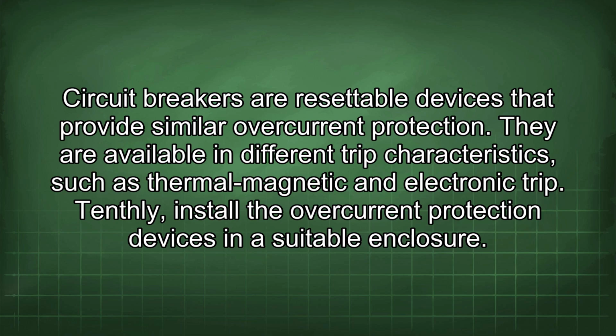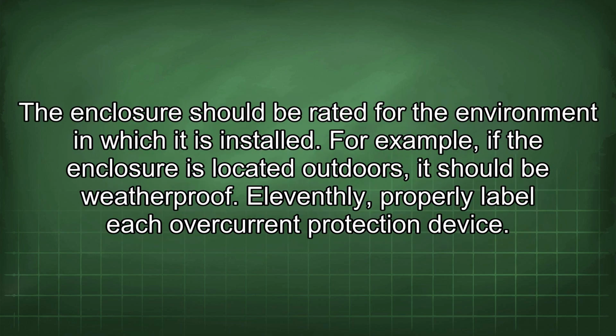Tenthly, install the overcurrent protection devices in a suitable enclosure. The enclosure should be rated for the environment in which it is installed. For example, if the enclosure is located outdoors, it should be weatherproof. 11thly, properly label each overcurrent protection device.